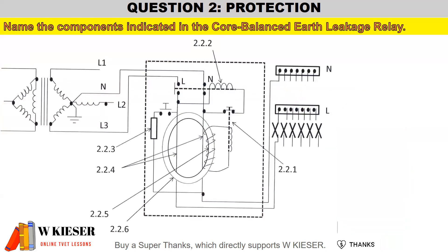In the following question, name the components indicated in the core balanced earth leakage relay. The core balanced earth leakage relay is used to detect an imbalance between the live and the neutral — in other words, a difference in the size of the current or the magnetic field on either the live or neutral phase. You only need a small current of 30 milliamps in order to trip the circuit.